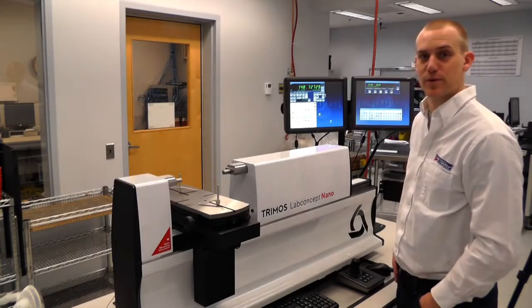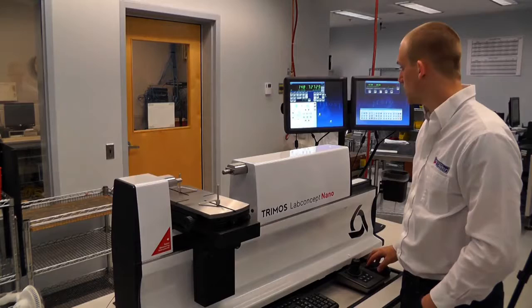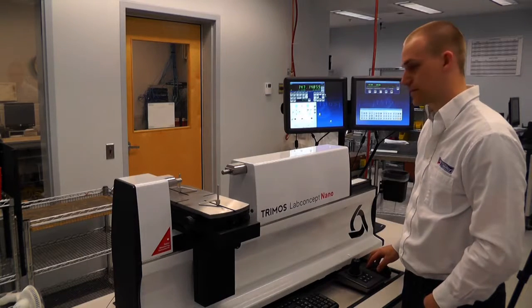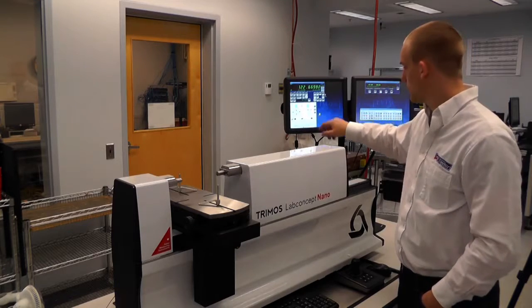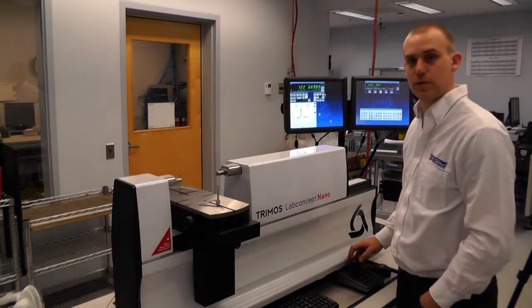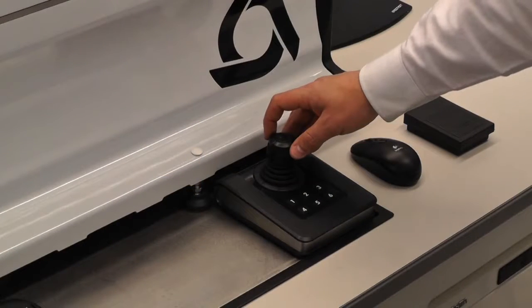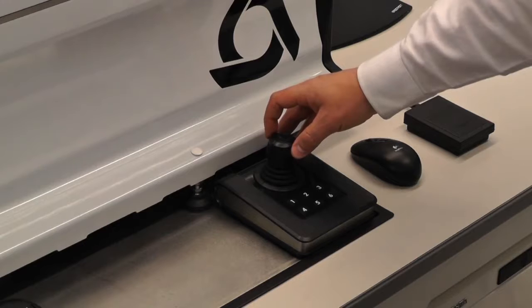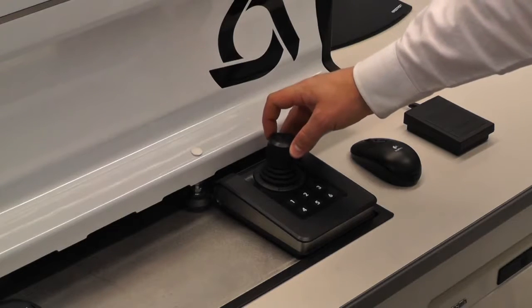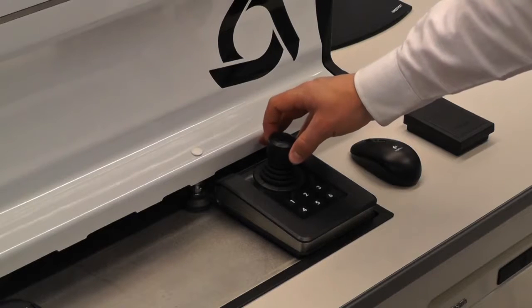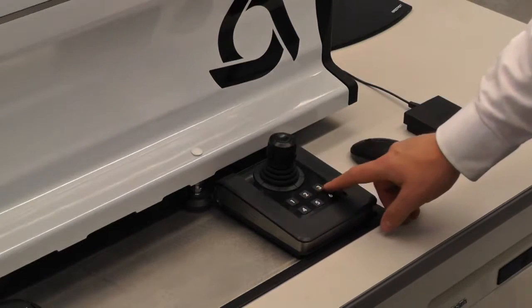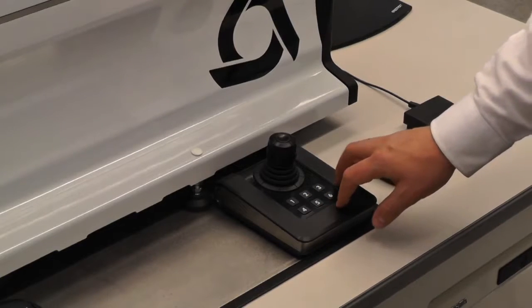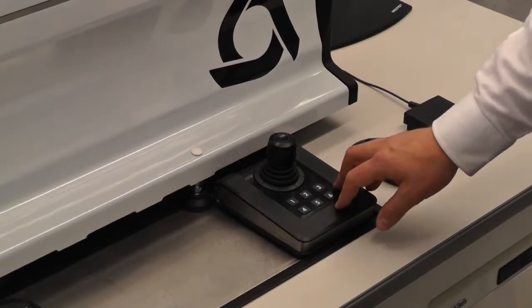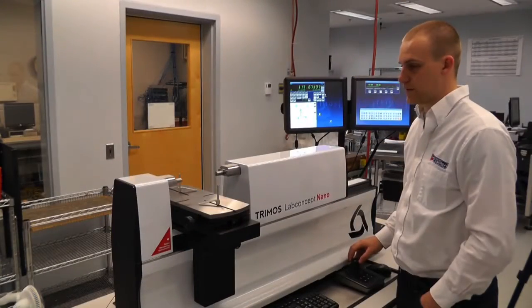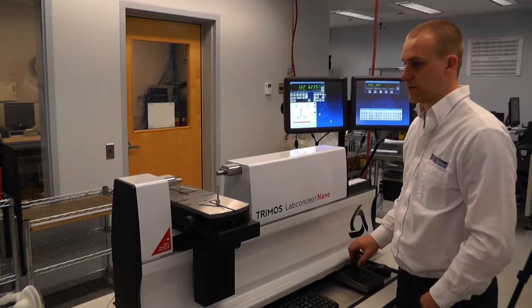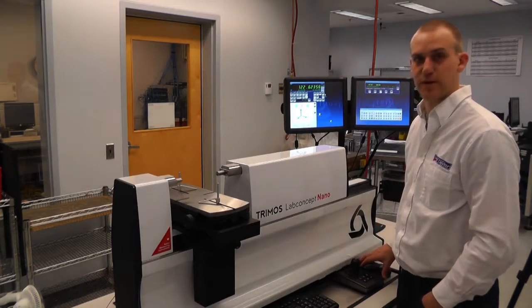In addition to the pre-programmed measuring modes, the machine can also be manipulated manually through use of a mouse, touchscreen, or alternatively, with joystick. Joystick control is as such: x-axis, left and right movement; the y-axis of the table, up and down; and the z-axis, twisting motion. There are also 6 pre-programmable buttons for certain functions such as external or internal measurement of a ring. All 3 degrees of freedom can be manipulated using these methods.